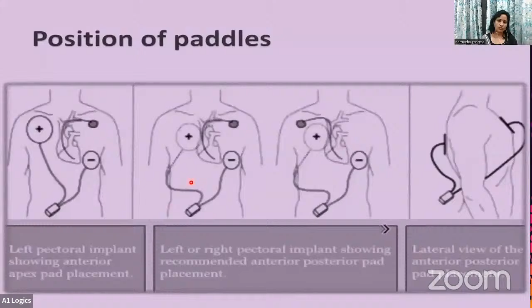Then what will you do if there are some intraoperative mishaps like arrhythmias? So first you have to ask the surgeon immediately to stop the surgery, stop all the electromagnetic interference, and then remove the magnet from the pulse generator. So this will automatically revert to the previous rhythm. Observe whether it is reverting to the previous rhythm within 10 to 12 seconds. If it fails, then you have to go with the external temporary pacing pads or the external defibrillation and resuscitation according to the ACLS protocol.